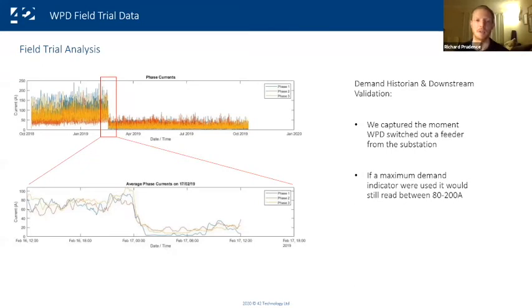In the data, what we noticed was a sudden drop in overall current. I remember when this happened there was a bit of a worry that maybe something we'd done with the programming of the controller had gone wrong, but we had in fact captured a real moment that WPD had switched out a feeder from that particular substation. We phoned them up and confirmed they had in fact done this on the 17th of February at midnight.